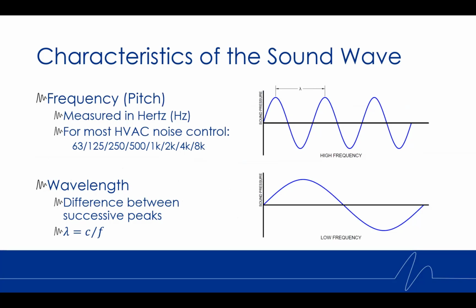So let's look at some of the characteristics of that sound wave. The first thing that we look at is either the frequency or the pitch. This is how often those concentrations of air particles happen. The closer they are together, the higher the pitch. The further away they are from each other, the lower the pitch, or the lower the frequency. When we work in HVAC noise control, very typically, we're going to be working in 8 different frequencies, 8 different pitches, or sometimes we call these octave bands as well. This is going to be 63 hertz, 125 hertz, 250, 500, 1000, 2000, 4000, and 8000 hertz. So generally, when we're talking about the sound power levels of a piece of HVAC equipment, we have that sound energy at 8 different frequencies.